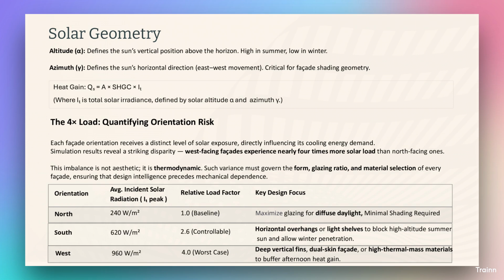Solar geometry. Altitude, alpha, defines the sun's vertical position above the horizon: high in summer, low in winter. Azimuth, gamma, defines the sun's horizontal direction, east-west movement, and is critical for facade shading geometry. Heat gain, Q equals A times SHGC times I, where I is total solar irradiance, defined by solar altitude alpha and azimuth gamma.